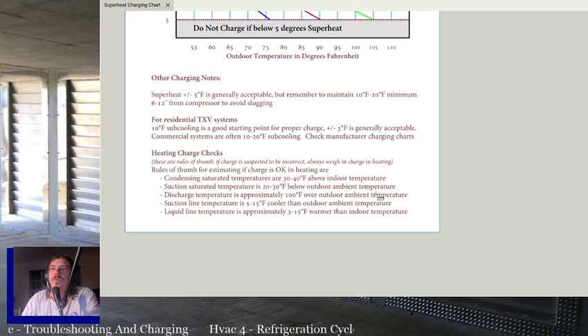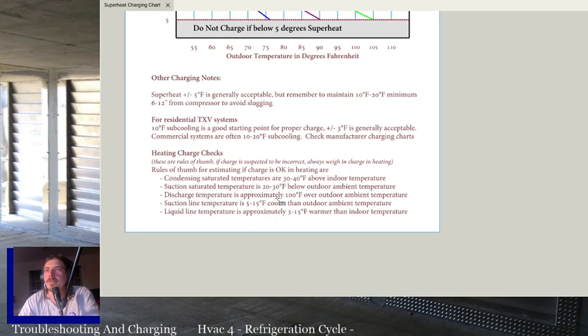The first two are what I would use to estimate where my pressures and my saturated temp should be. The discharge is just one of those rules of thumb that float around and people seem to think it works. And then your suction line temp, 5 to 15 cooler than outdoor ambient. Again, it should be a little bit lower than outdoor ambient because we're still trying to superheat using that outdoor air, but it should be pretty close. And then liquid line temperature is approximately 3 to 15 warmer than indoor temperature because we're giving off heat to the inside and we're trying to subcool that. So we're going to be 3 to 15 warmer by the time it's all said and done.